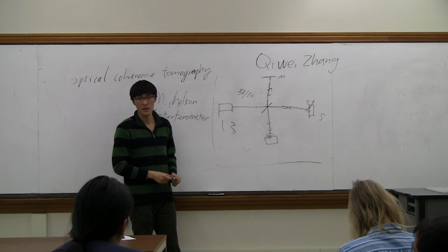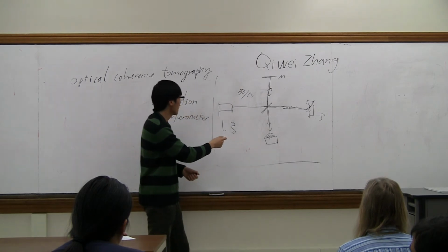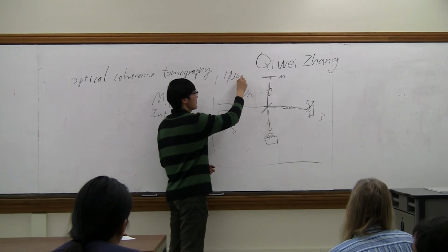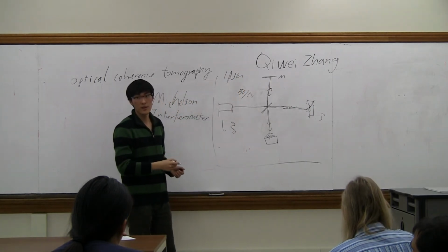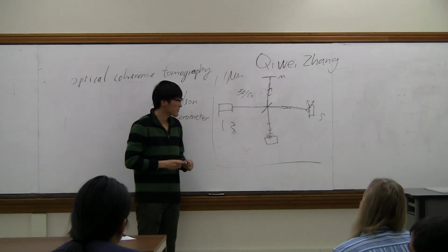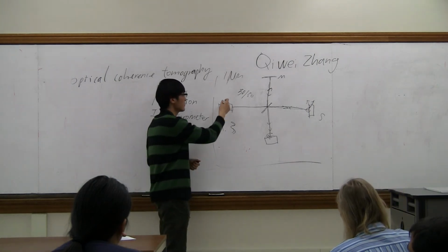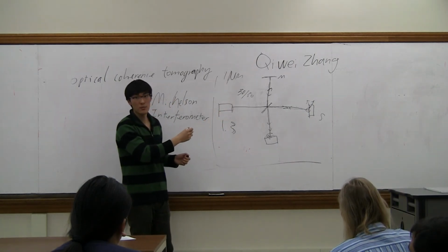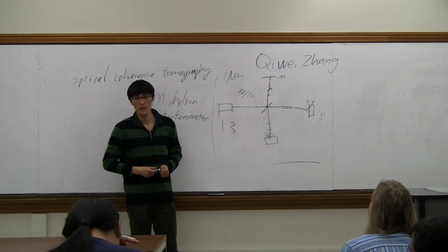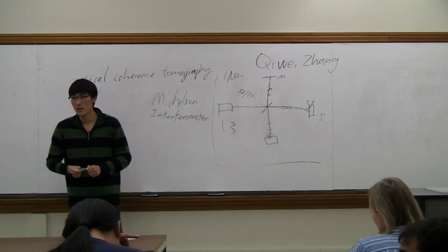So what is the depth resolution? With 1.3 micrometer, the resolution can be 1 micrometer. What color light is it? Is this a UV laser? No, white light is okay because we use the broadband. Why would you not use a laser? Why would you prefer a broadband?